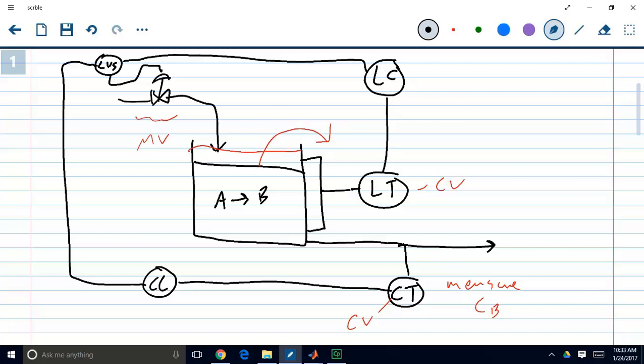So the control scheme that we attempted to set up was to control concentration using flow rate, and we would use our level controller as an override. So if the level got so high that it threatened to overflow the tank, then this level controller would kick in and would reduce the flow rate, and we would no longer be in concentration control.